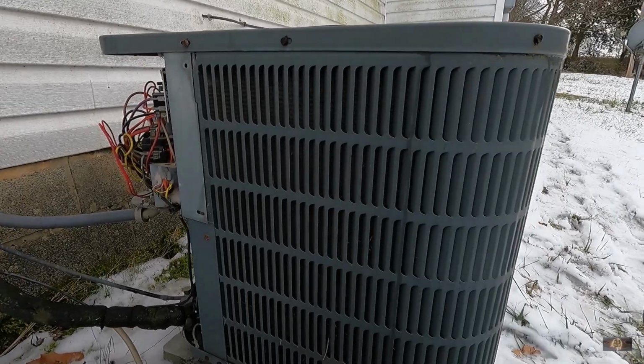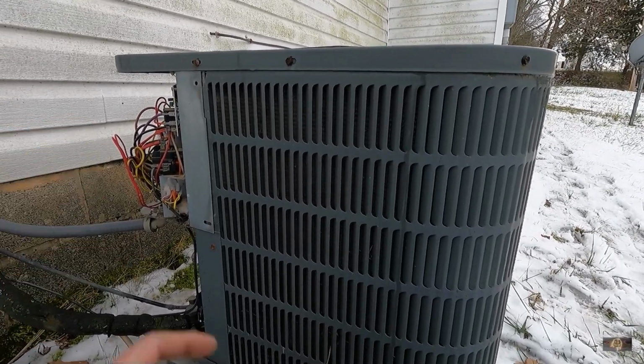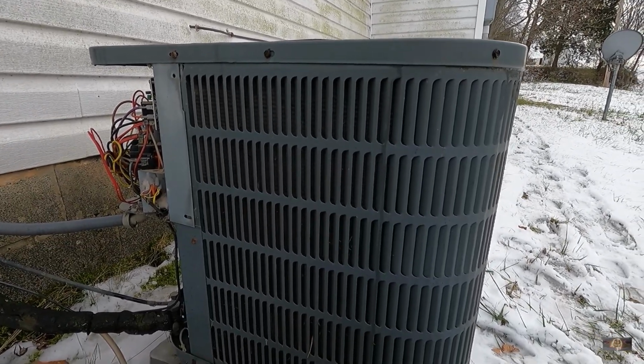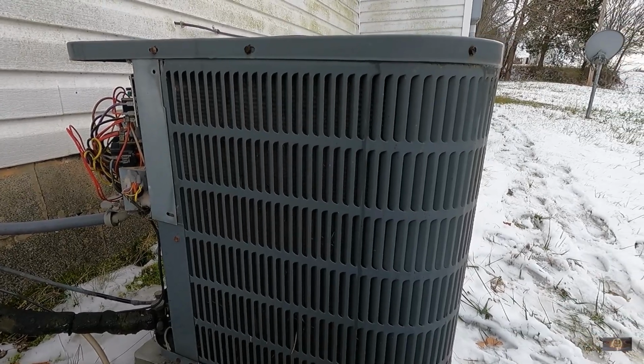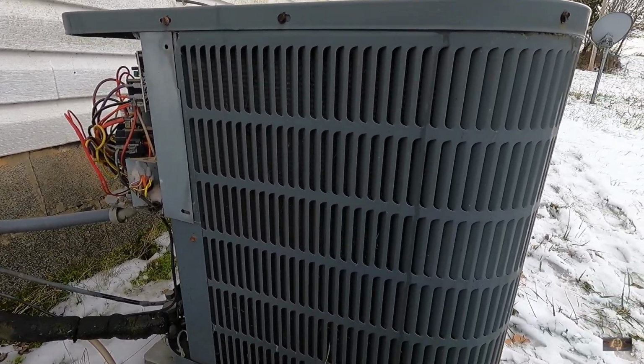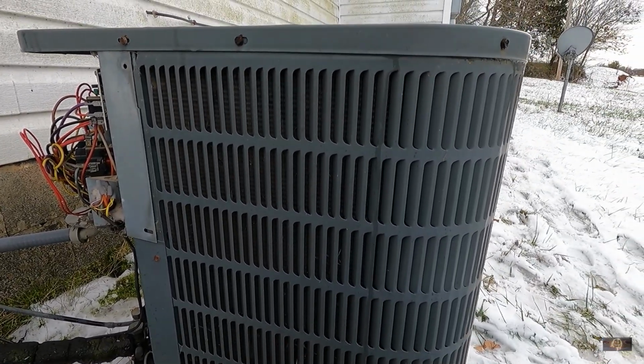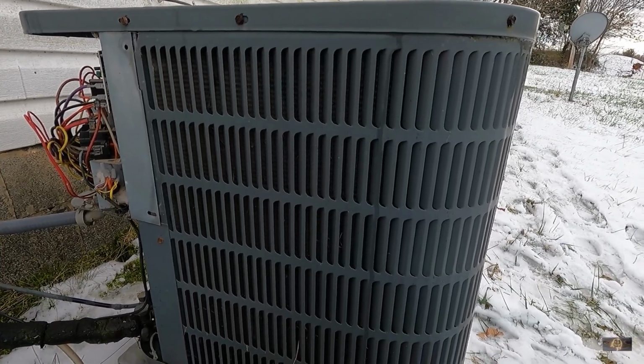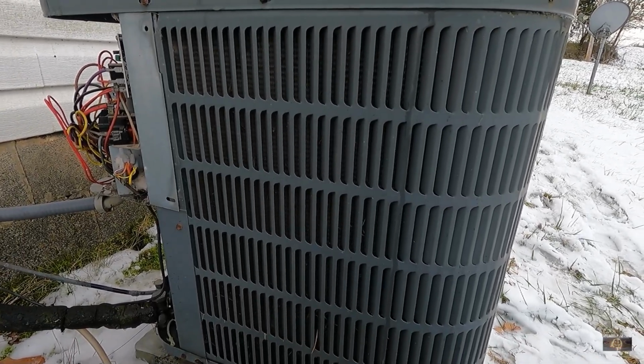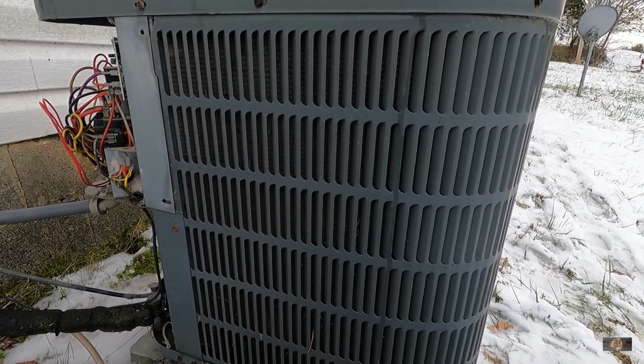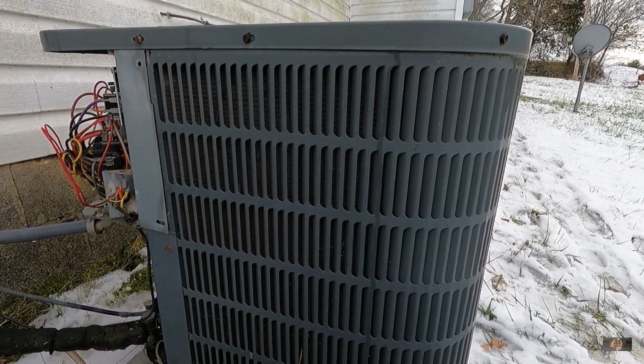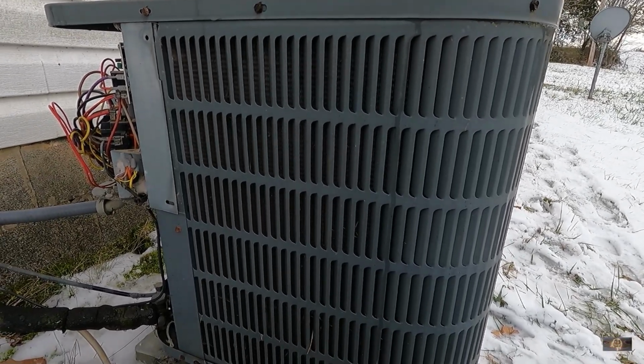Okay, the unit went into defrost here. It's set on an accumulated runtime of 30 minutes. Could probably get away with 60 here, but I asked if they wanted to change that. They said they want to keep it. They are kind of up here in the mountains a little bit. So it's defrosting right now. I'm going to make sure that it comes out of defrost. I didn't hear anything out of the ordinary there.